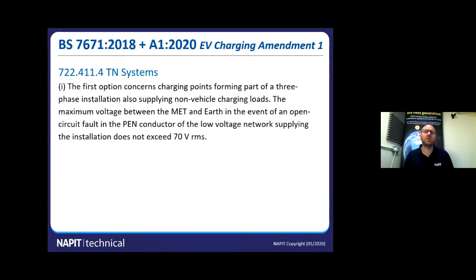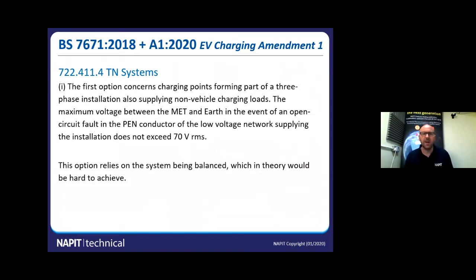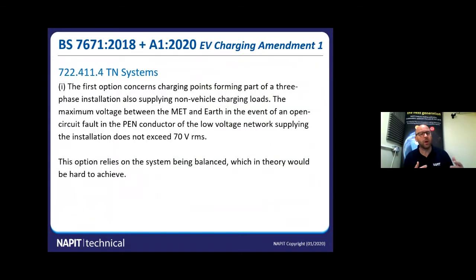So the first requirement, or first method, concerns charging points forming part of a three-phase installation that's also supplying non-vehicle charging loads. In the event of a fault in the PEN conductor, what we're trying to achieve here is that we don't get 70 volts touch voltage. So what this requirement is looking for is a balanced three-phase installation where there's not much current flowing in the neutral. Okay, so it's quite hard to meet, because as we design installations, if it's a new build, you're going to have all of the loading considerations mapped out for the design.